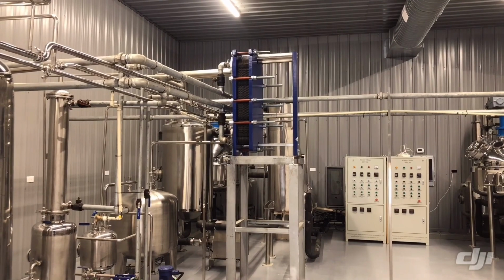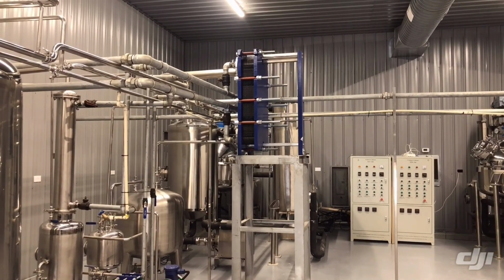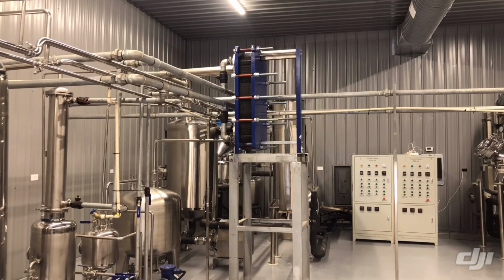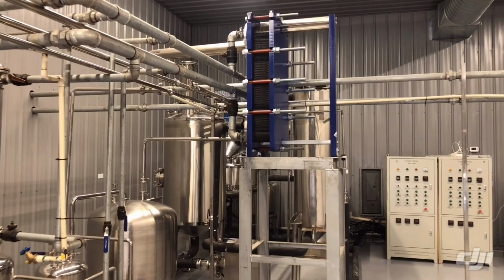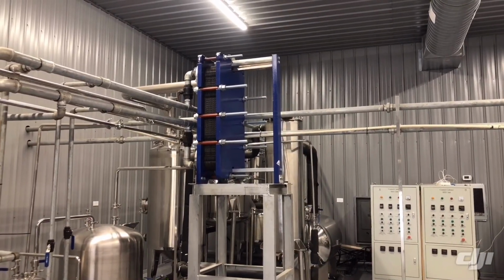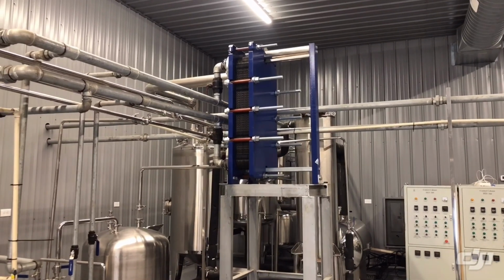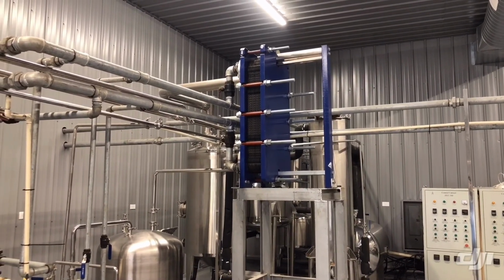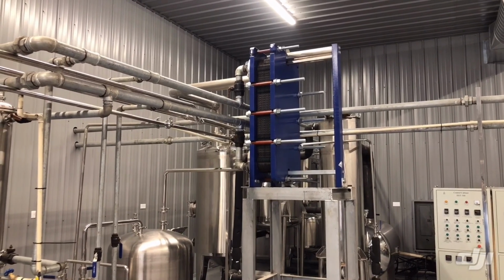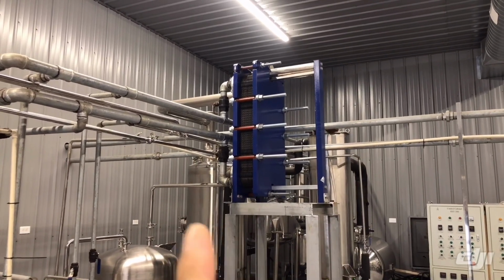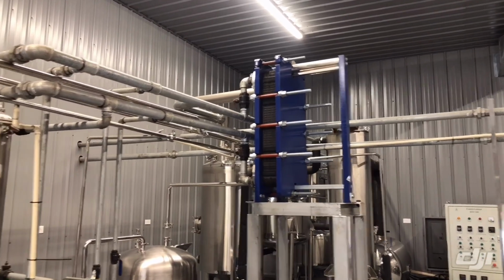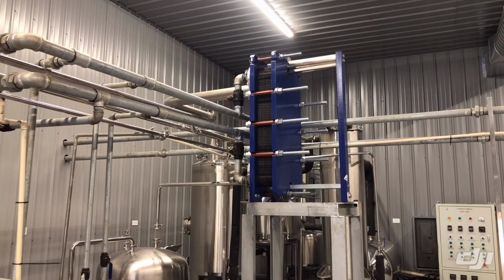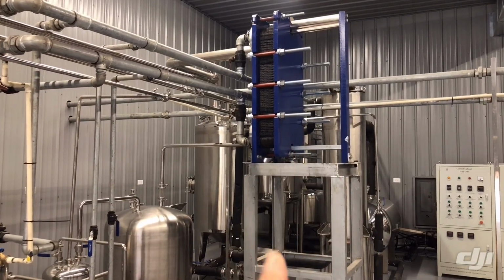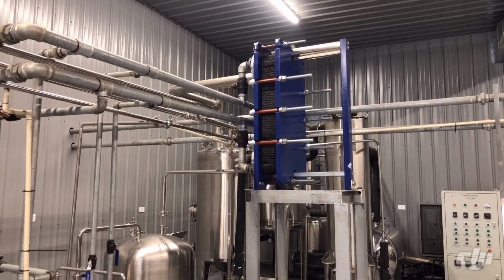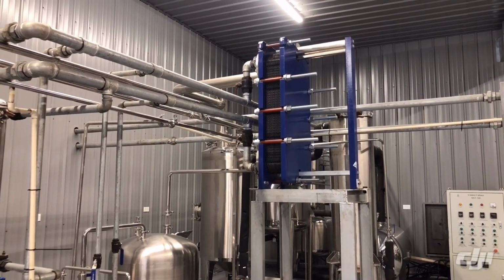Oh, also there's another part that is not so well designed right here. So you see the heat exchanger right there. That one is cooled by the water tower that is located next door, and the water tower can only cool the temperature down to about 15 C, which is the water temperature of your local water source. It cannot reach lower than that, but for chilling down the ethanol, the lower the better. If the temperature can reach down to 5 degrees Celsius, then the recovery rate of the ethanol will be improved significantly. So what I would suggest is that you get a 2-stage heat exchanger, and put another heat exchanger down there that is supplied by the chilled water chiller.